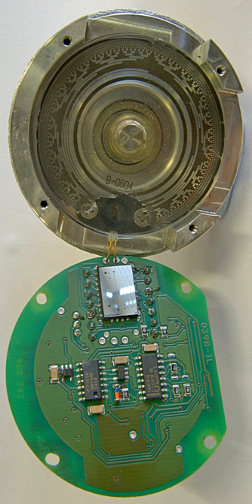Because of this, incremental encoders are commonly used in applications that require precise measurement of position and velocity. A rotary incremental encoder may use mechanical, optical or magnetic sensors to detect rotational position changes. The mechanical type is commonly employed as a manually operated digital potentiometer control on electronic equipment. For example, modern home and car stereos typically use mechanical rotary encoders as volume controls. Encoders with mechanical sensors require switch debouncing and consequently are limited in the rotational speeds they can handle. The optical type is used when higher speeds are encountered or a higher degree of precision is required.